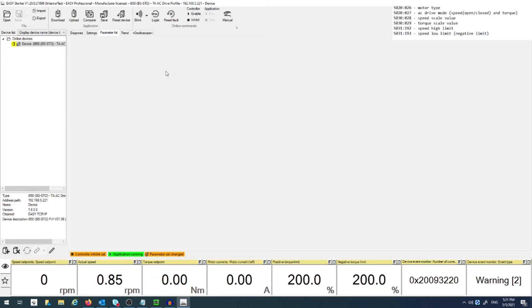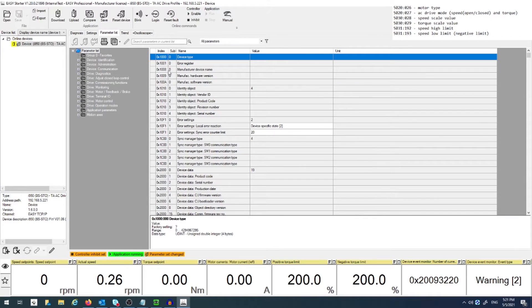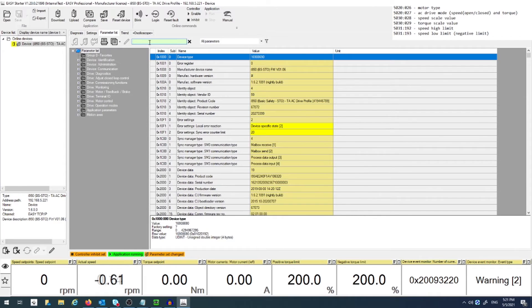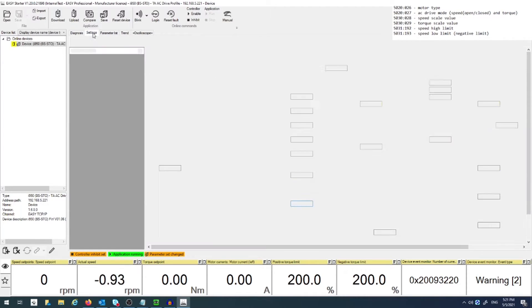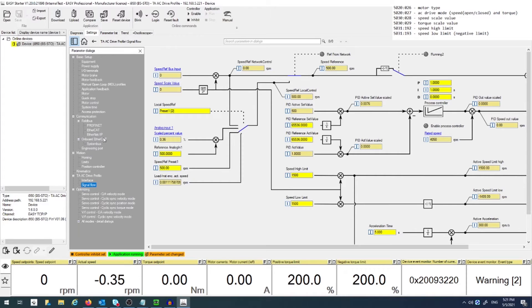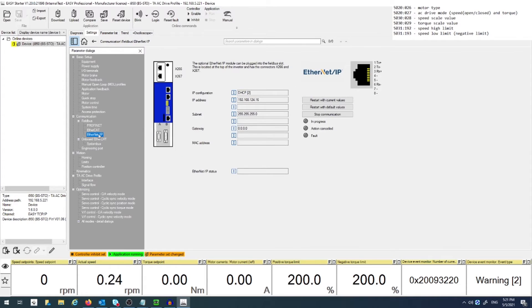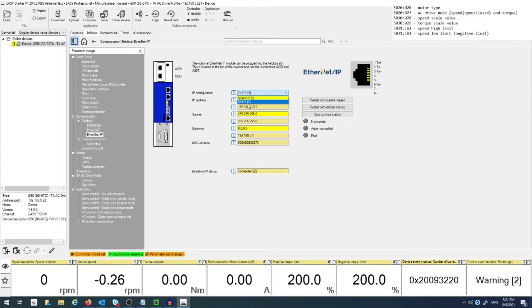These parameters can be searched for in the Parameter List tab, and you can also add them to your Favorites folder for future reference. Lastly, go into the Ethernet IP section to set up your IP configuration so that it can communicate with your PLC. You can do this using DHCP or by manually storing a fixed IP address in the drive.